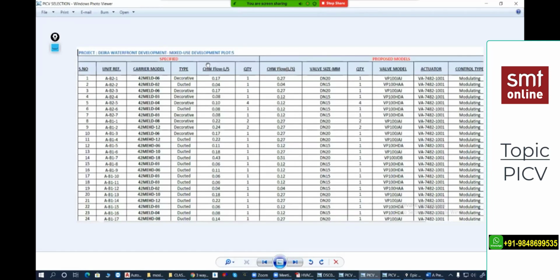Is there a catalog on how we can set the range? Yes, any manufacturer will provide the catalog. But what I'm trying to say is this is very simple compared to the three-way and two-way valves. Three-way and two-way valves are set at the time of commissioning by service people only. But this can be done by the installation people also. Anyhow, at the time of commissioning they must verify, and they will check whether you installed the proper model of this PICV or not. They will check the reading. But at the time of installation, or before installation, we can also set. So this is easy in comparison.